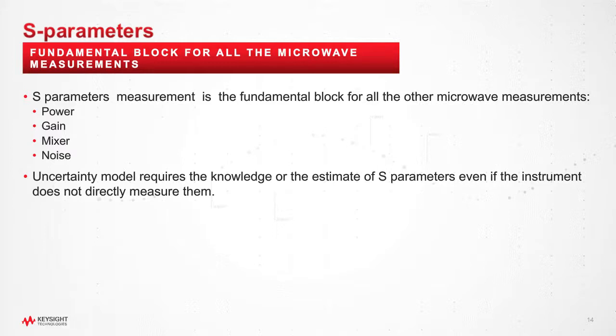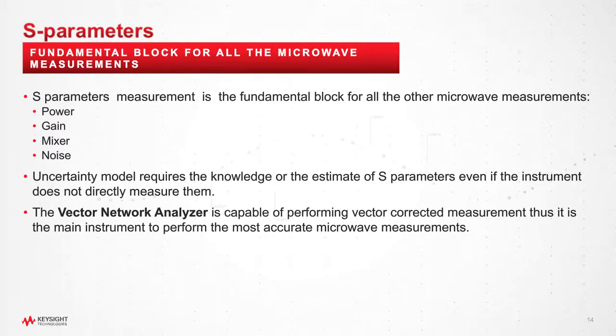Let's say that you have a simple power meter. To compute the uncertainty of a simple power meter output, you need to know somehow the uncertainty linked with the reflection coefficients and transmission coefficients, which are S parameters. And thus, the uncertainty of the final power will be a function of how you estimate your S parameters. In this talk, I'm going to talk about the VNA. Why am I talking about the VNA? Because the VNA is capable of performing vector corrected measurements. Thus it is the main instrument to perform the most accurate microwave measurements.